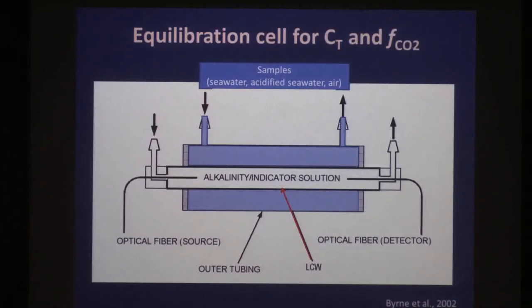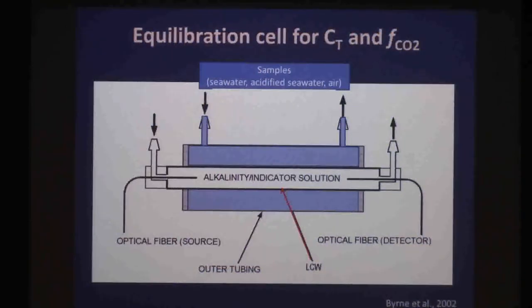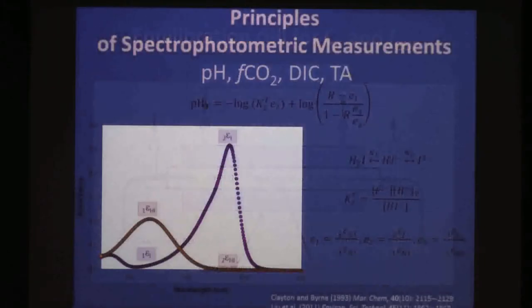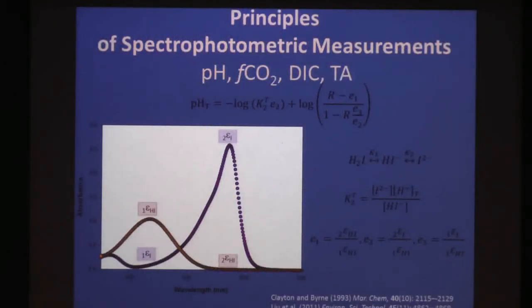This shows a schematic of exactly what I'm describing: fiber optics coming in and out of the system — one carrying light in, the other taking light to the spectrophotometer. This is the liquid core waveguide, this is our alkalinity indicator solution which we can replenish from time to time, and this is the outer solution — seawater that we acidify for determinations of dissolved inorganic carbon.